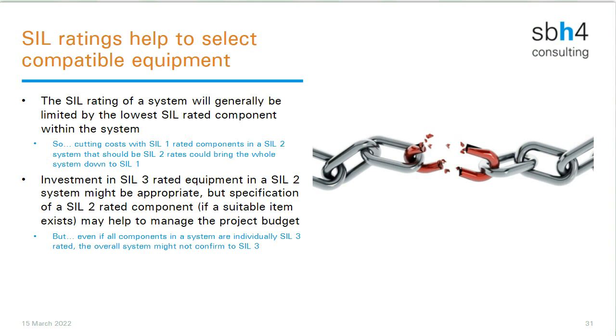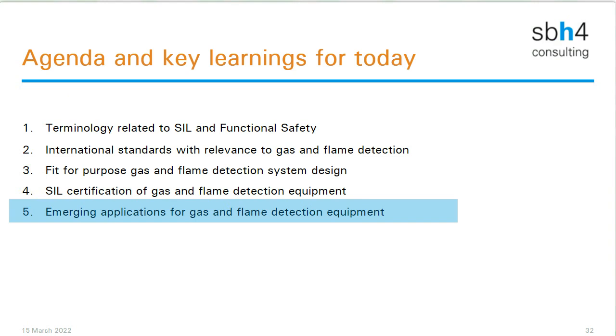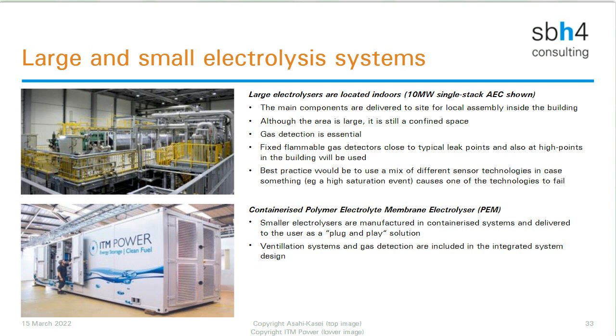So we're moving on to something a little bit different now. We're looking ahead to emerging applications of gas and flame detection equipment. Let's take an example of hydrogen electrolyzers. And the two photographs here, top and bottom, show you a very, very large hydrogen electrolyzer, a 10 megawatt single stack atmospheric pressure electrolyzer from Asahi Kasei installed in Japan. And the lower photograph, a containerized unit. This one is an example from ITM Power, and this is still in their factory prior to shipment.